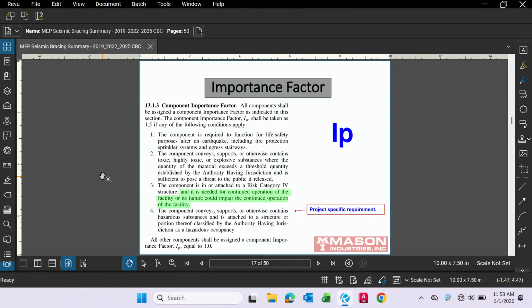Keep in mind that on some projects, the owner or design team can choose to override these requirements. They can decide to upgrade or amplify the importance factor to 1.5 for all their components. What that does is increase the design seismic force we have to design for all the components, and the importance factor also plays a big role later on in what needs to be braced and what can be exempted.